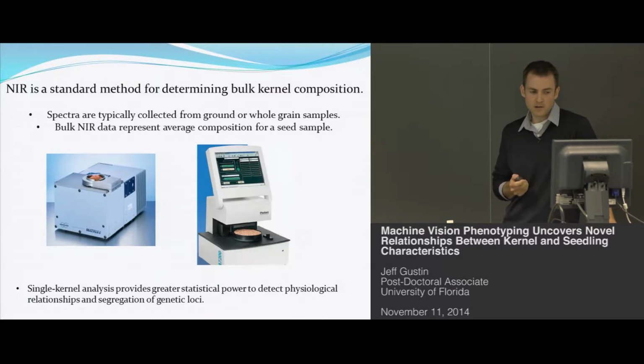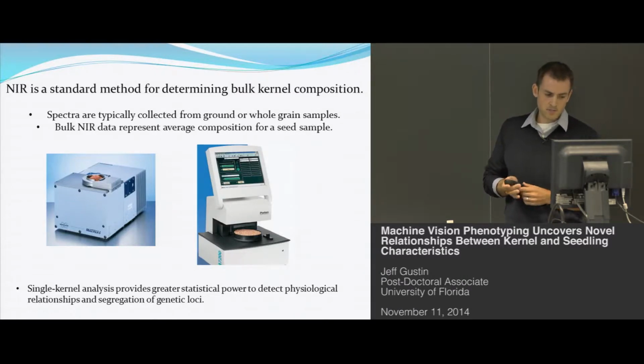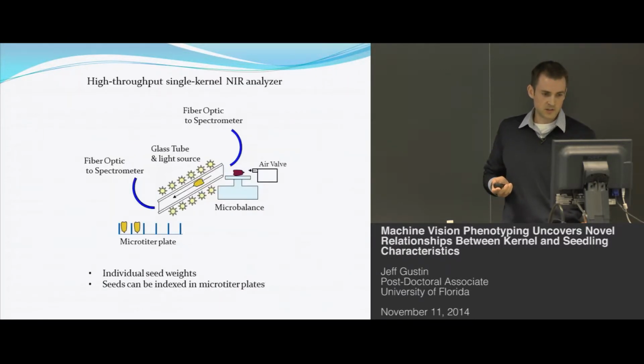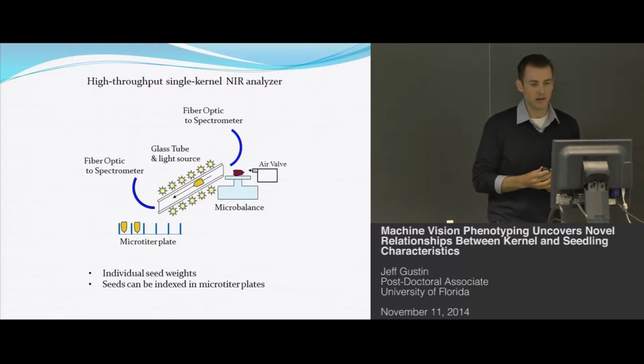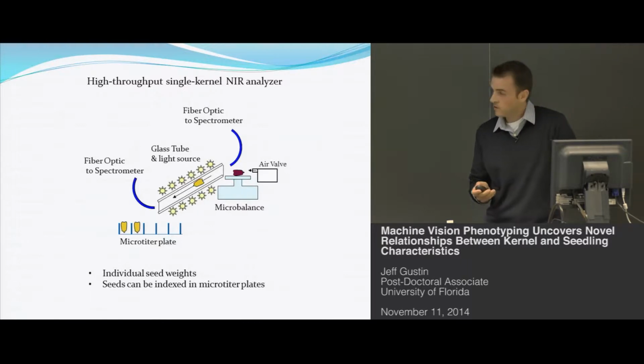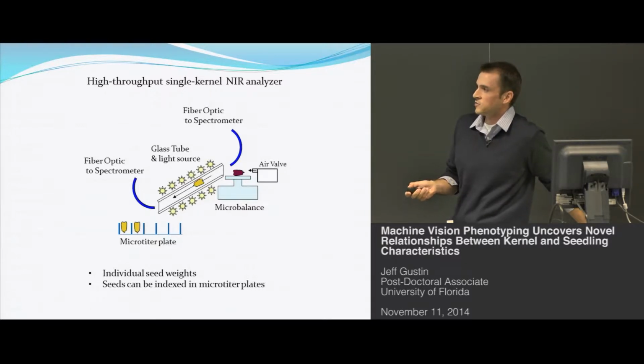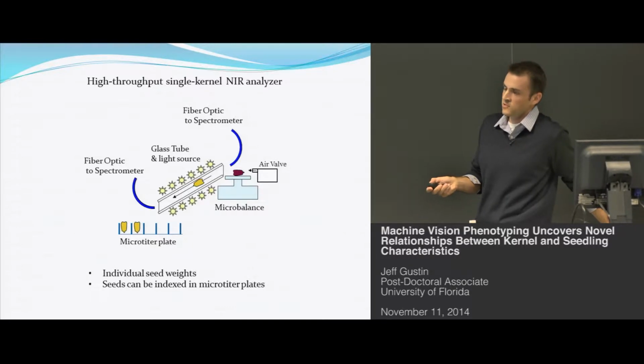But we wanted to scale down this technology to allow you to measure single kernels, which allows you to do much better, allows you to do genetic studies on segregating material. And so this is a schematic of our single kernel NIR machine. The process for measuring a single kernel is, first, the kernel falls onto a microbalance where a weight is collected. A puff of air pushes that kernel down an illuminated light tube. That tube is illuminated by 50 halogen lamps, which are these little sun-like objects up here.